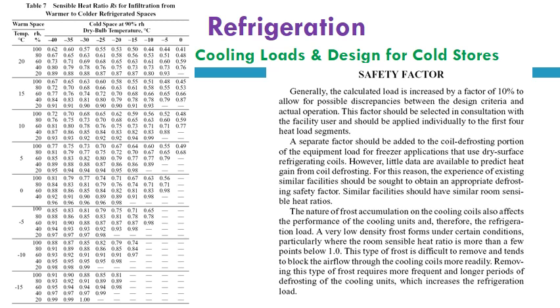We have to take into consideration this difference between the actual operating hours, which is commonly taken as 18, and that gives about 6 hours from the 24 hours to make the unit standby, shut down the equipment, and activate the defrosting devices such as electrical heaters. So the equipment should be sized to carry the load of 24 hours in 18 hours by multiplying the final estimation and summation of the cooling load of the first four segments discussed before by 24 divided by 18 hours in this case.